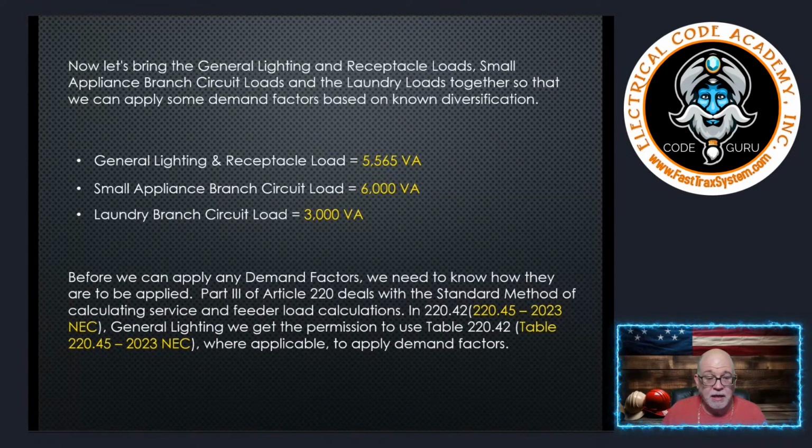Now, again, if it's a multifamily building that has a laundry facility on site, then you have some allowances to not put the laundry receptacle in because it's available to all the tenants or all the people at the complex, and there's a separate laundry facility. Then that's different. Then you don't have to install the receptacle at all, but you're required to have the laundry circuit. And in a single family dwelling, you're required to install the laundry receptacle outlet. Okay? And I believe that is in 220.52D, if I'm not mistaken.